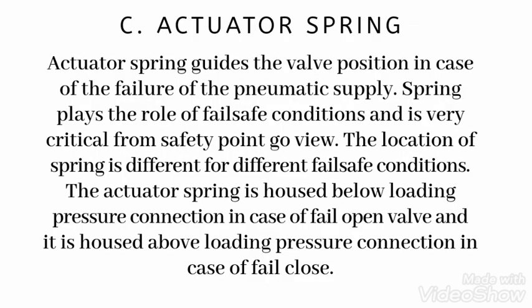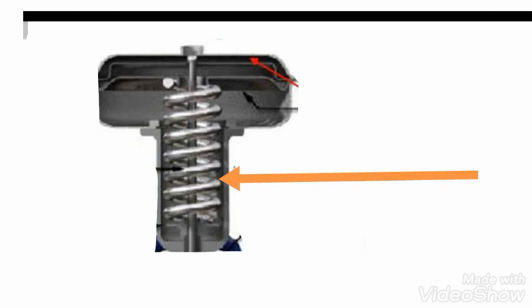The actuator spring guides the valve position in case of failure of the pneumatic supply. The spring provides the fail-safe condition and is very critical from a safety point of view. The location of the spring differs for different fail-safe conditions. It is housed below the loading pressure connection for a fail-open valve, and above it for a fail-close valve. Here you can see the spring is below the diaphragm — this is a fail-open valve because when there is no air, the spring pushes the diaphragm upward and makes the valve open.